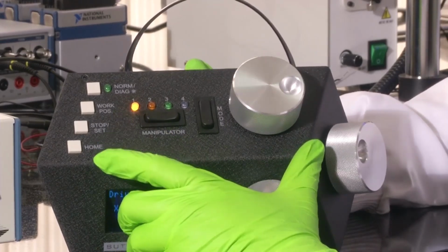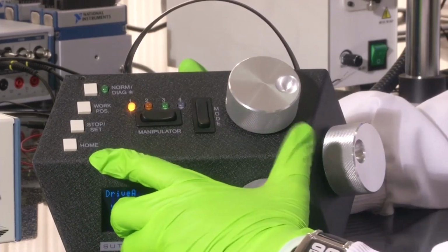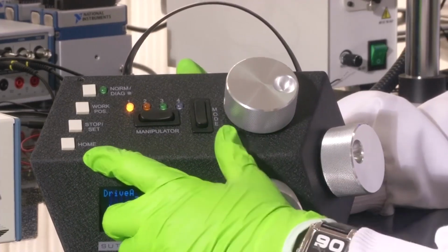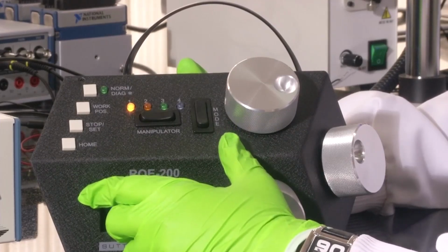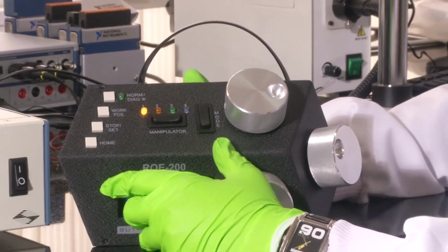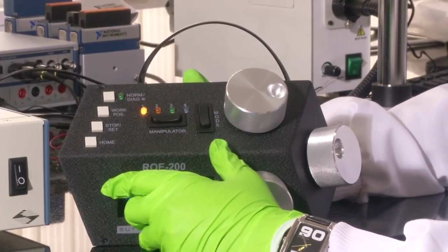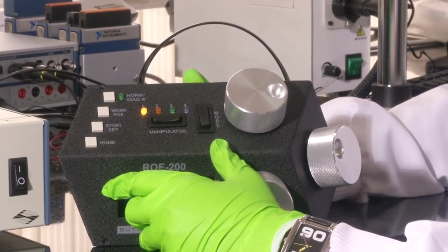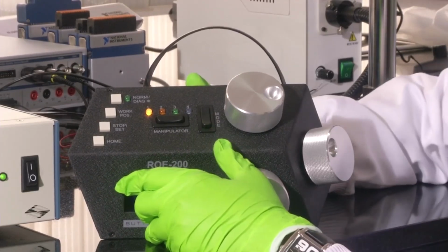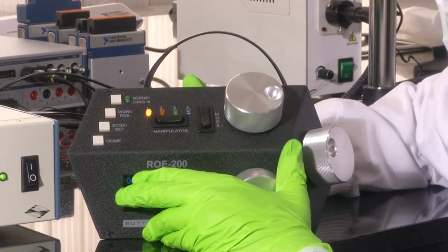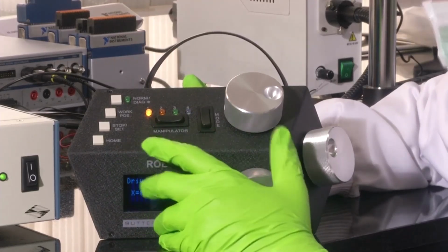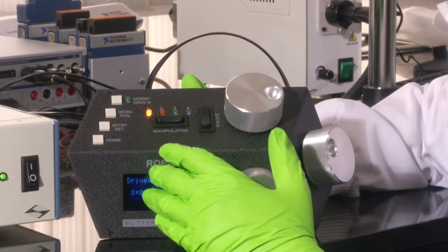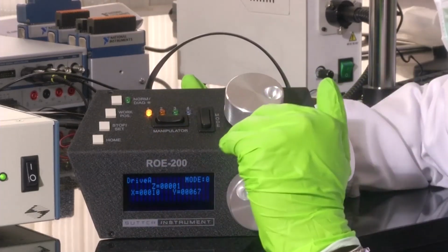Okay. So, let us say we have started manipulating the manipulator by changing the knobs and you arrived at a position. Let us say X is 15,000, Y is 10,000 and Z is 20,000 in microns. As you must remember, the X, Y and Z directions can navigate from 0 microns up to 25,000 microns or 25 mm. And you have reached these values. At this value you are able to indent your sample properly, and then suddenly you got some other work and had to rush out, and then for you to search and seek out this place again is difficult. So, you can always save your work position here.